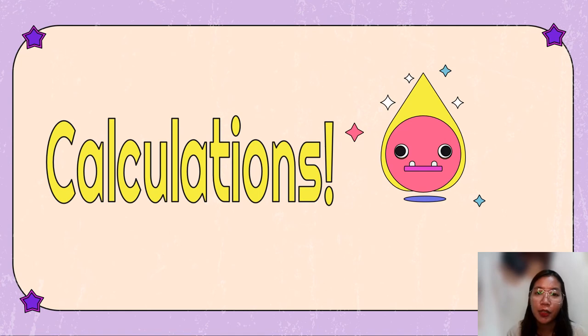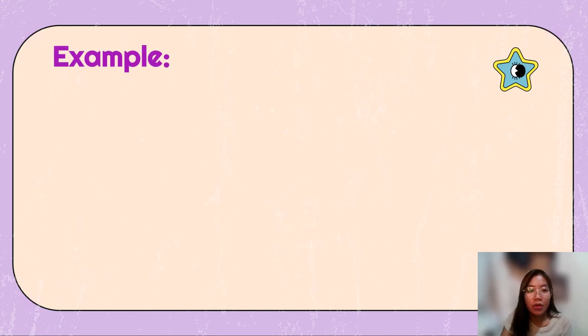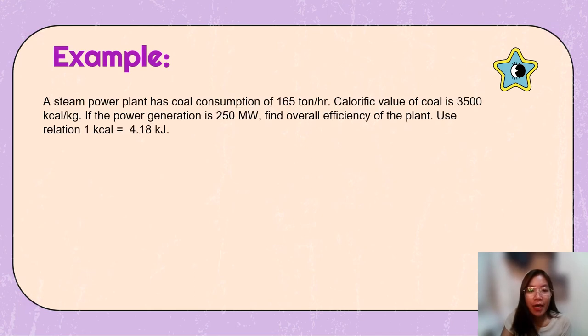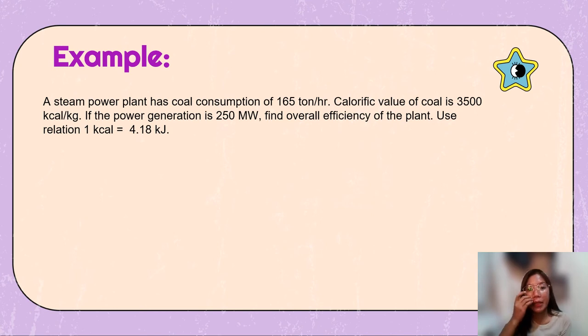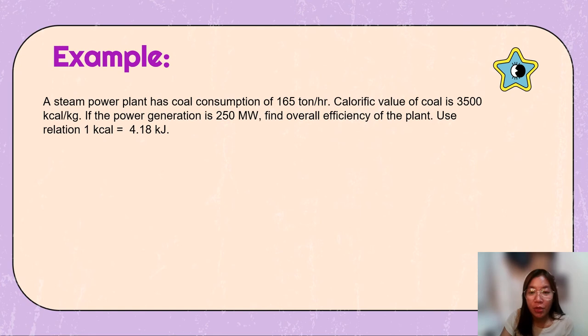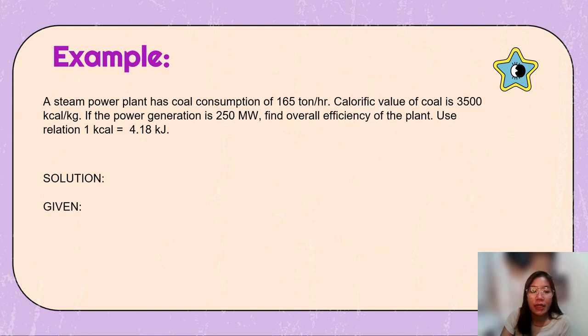Now we have the calculations. A steam power plant has a coal consumption of 165 tons per hour. The calorific value of coal is 3,500 kcal per kilogram. If the power generation is 250 megawatts, find the overall efficiency of the plant. Use the relation: 1 kcal equals 4.18 kJ.